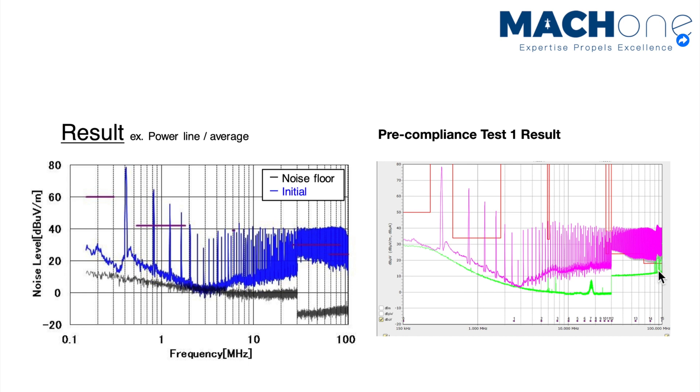We picked up strong radio FM noise. This is due to the fact that we have a big broadcasting tower, only about 15 kilometers away from where we live. So we picked up the ambient noise, and as you can see here, the conducting emission results showed slightly higher, compared to this one, because of the ambient noise.